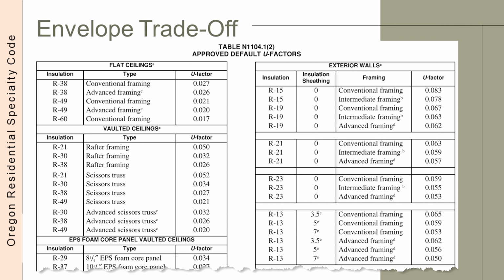Let's look at a flat ceiling construction with a vented attic and R60 insulation using conventional framing. This is a ceiling that has a U factor of 0.017. The designer, if using this trade-off, would put the U 0.017 value in the proposed alternative column. This table has lots of options for walls, both with and without continuous insulation. R23, usually a dense packed blown-in insulation, is becoming more commonplace. The U factor for R23 insulation in intermediate framing is 0.055.